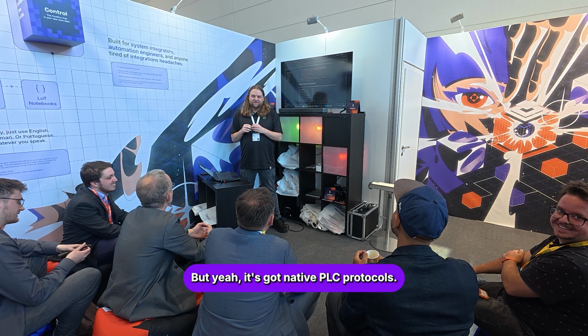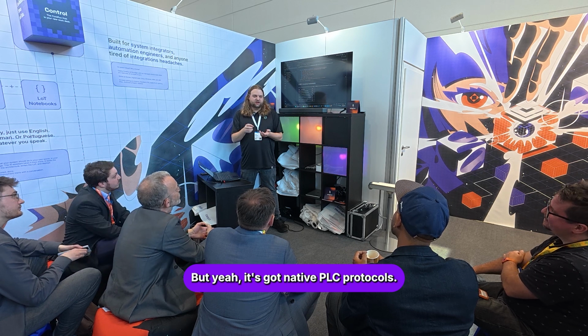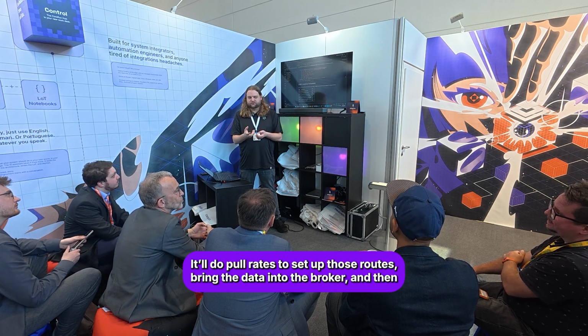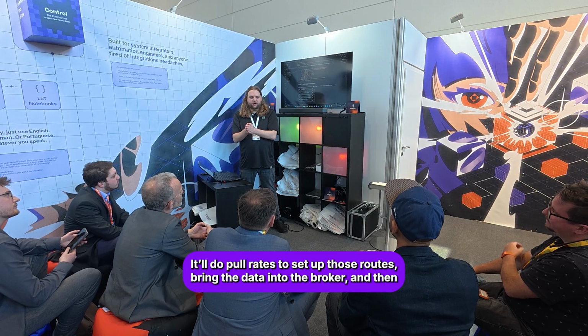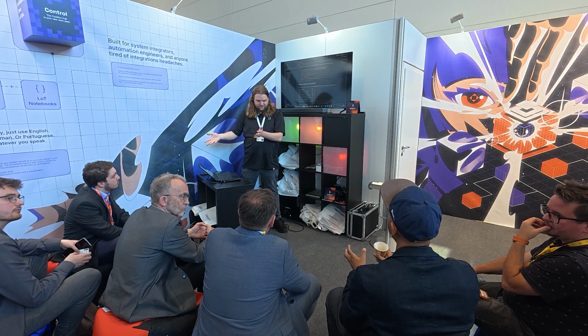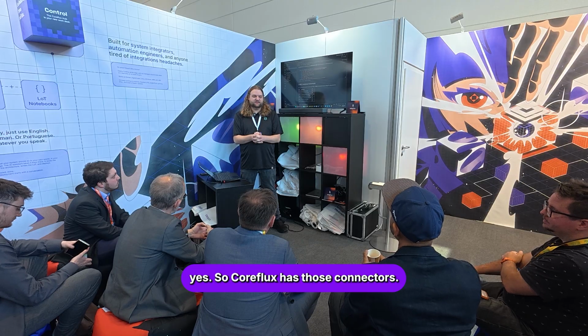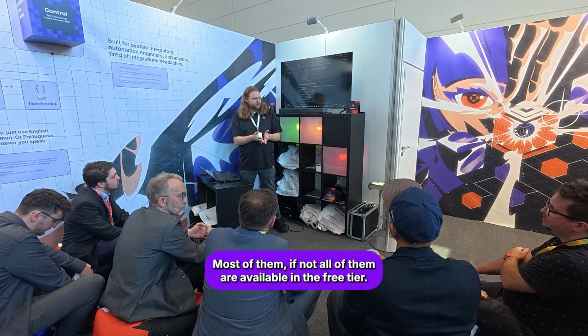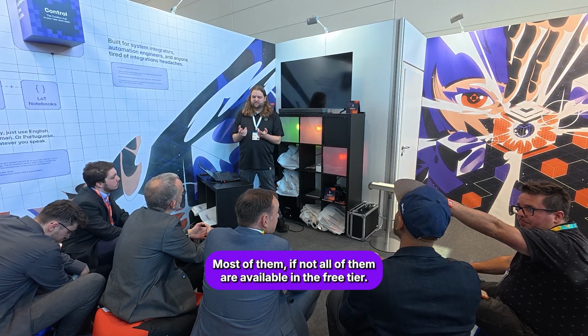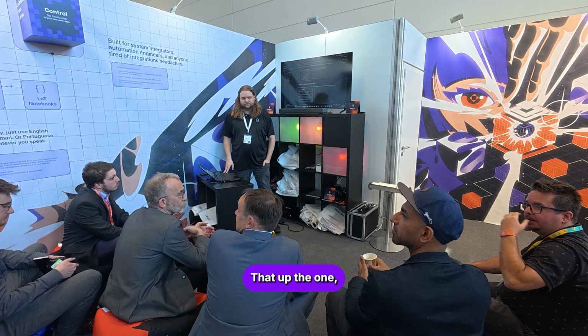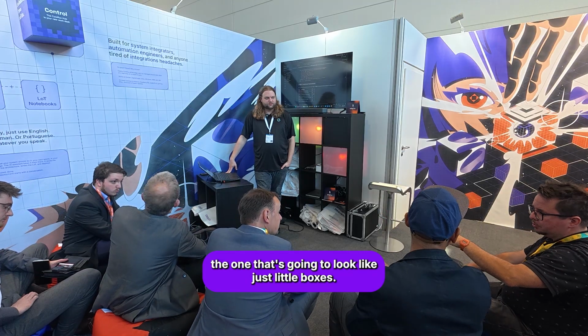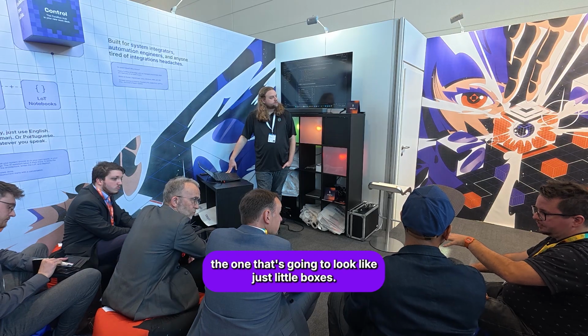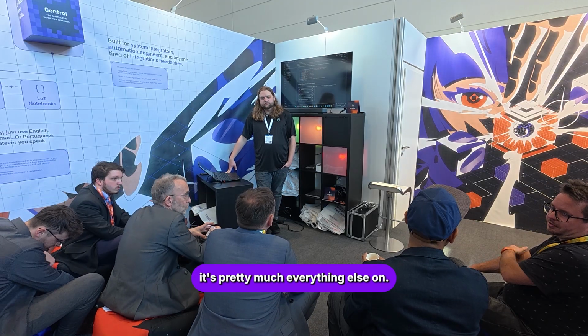But yeah, it's got native PLC protocols. It'll do poll rates, you set up those routes, bring the data into the broker, and then, yes, so Coreflux has those connectors. Most of them, if not all of them, are available in the free tier. The one that we're currently working on for industrial purposes, it's not yet available directly, it's SparkPlug. Pretty much everything else is already.